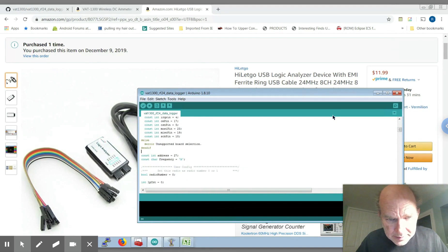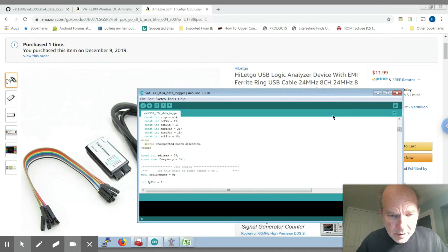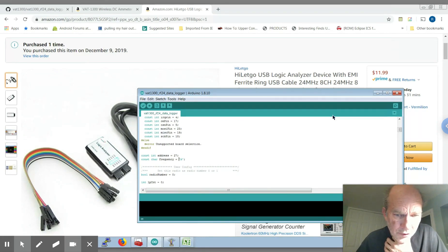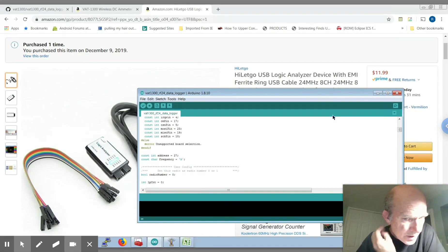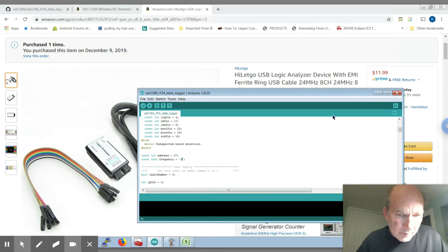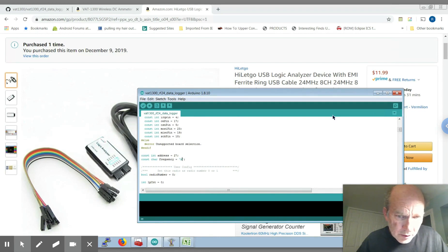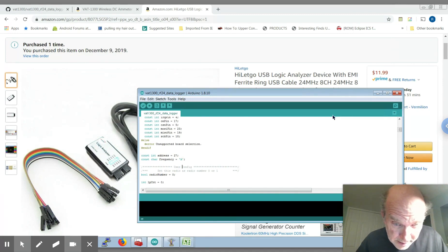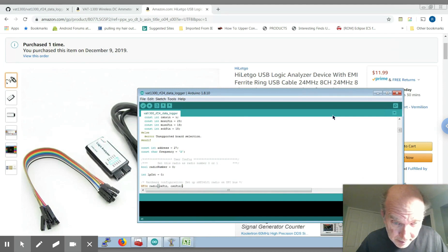And then these are important, these address and frequency, those are the address that shows up on the top of the Gentech controller. So in this case the address and frequency was A27. So change this to whatever your particular unit is configured for. And it is case sensitive so make sure the frequency is the capital character.